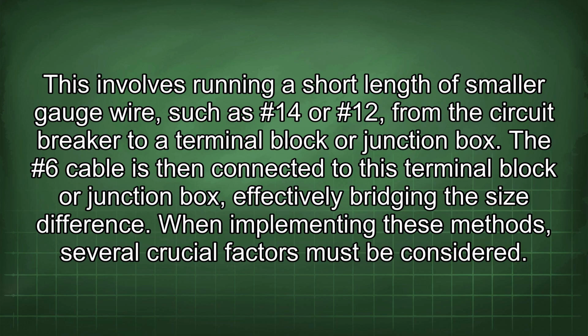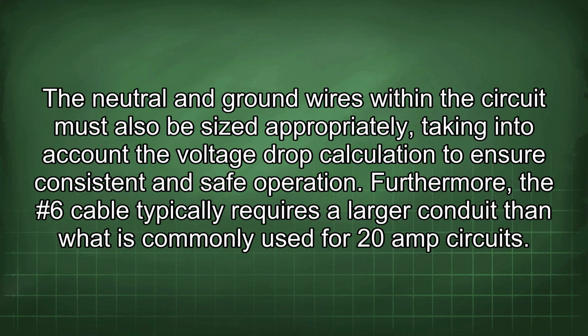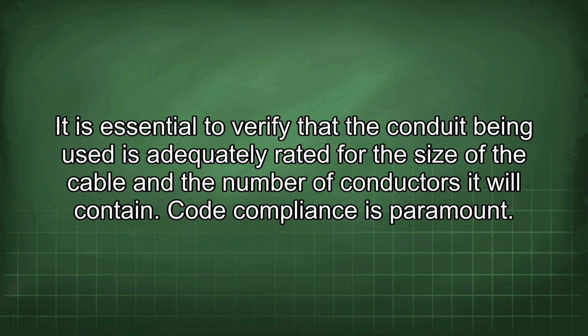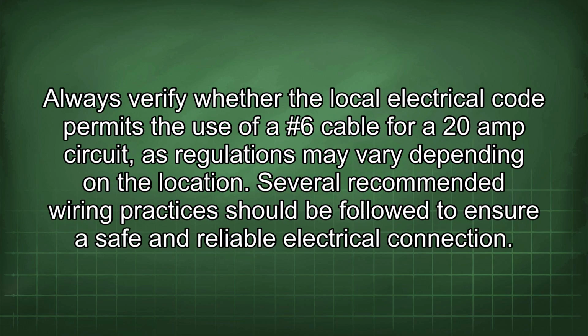When implementing these methods, several crucial factors must be considered. The neutral and ground wires within the circuit must also be sized appropriately, taking into account the voltage drop calculation to ensure consistent and safe operation. Furthermore, the #6 cable typically requires a larger conduit than what is commonly used for 20 amp circuits. It is essential to verify that the conduit being used is adequately rated for the size of the cable and the number of conductors it will contain. Code compliance is paramount. Always verify whether the local electrical code permits the use of a #6 cable for a 20 amp circuit, as regulations may vary depending on the location.